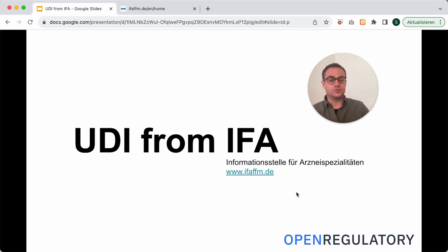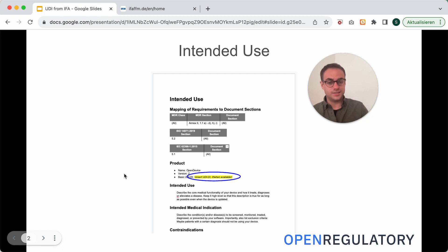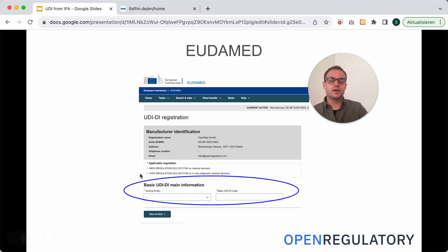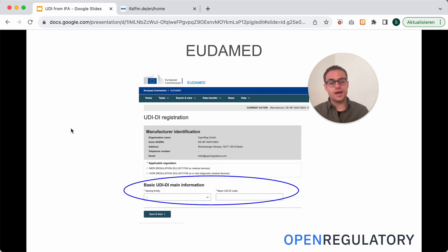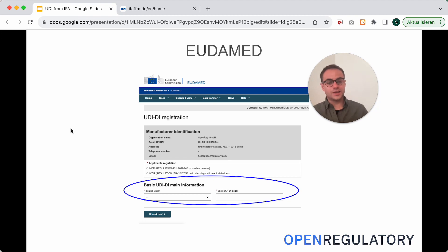The basic UDI-DI is the number that goes into your documents — like your technical documentation and your intended use — and it describes the general product you're certifying. You also need it for the EUDAMED database, where you register all your devices, and for communication with your notified body and competent authority. Apart from the basic UDI-DI, you also need a UDI-DI specific for every major version of the device you release, and a UDI-PI that's unique for every single piece of your device.